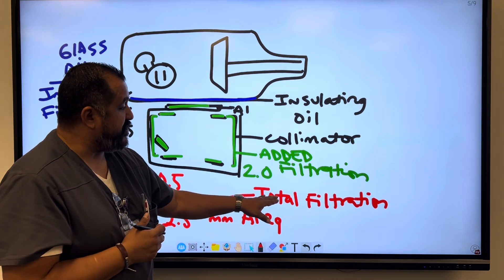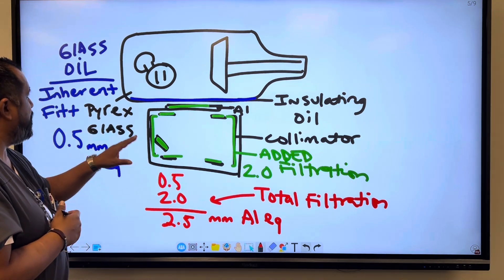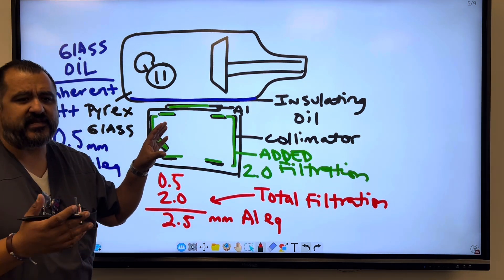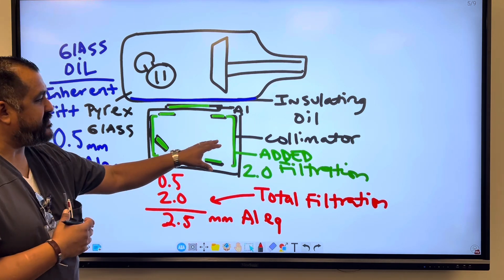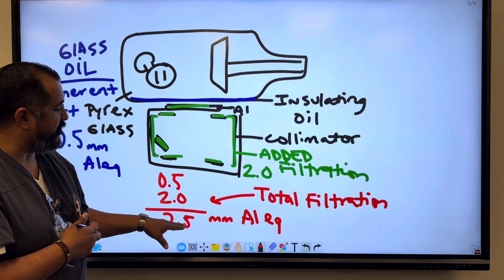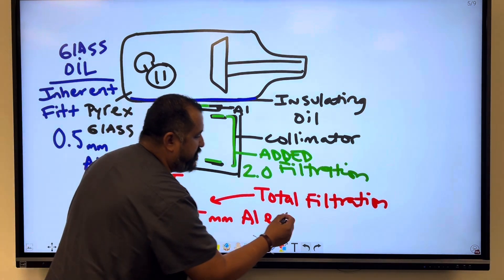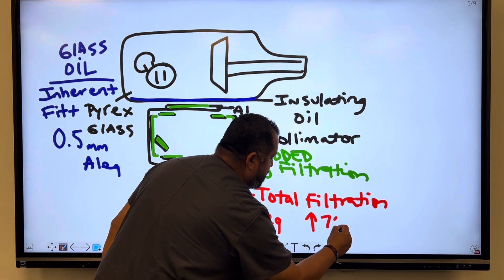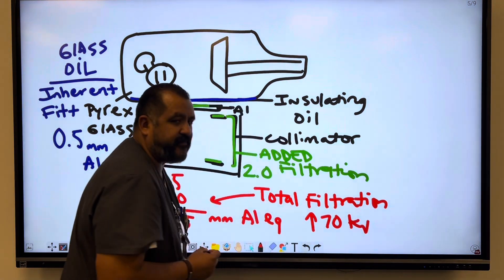So total filtration, again, is the combination of the inherent - and inherent means built in or manufactured in - and added, something that we add to it. So the total filtration is 2.5 millimeter of aluminum equivalent, because we operate with systems that go above 70 kVp.